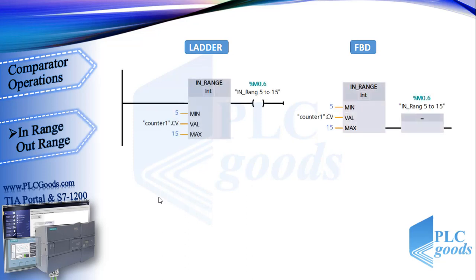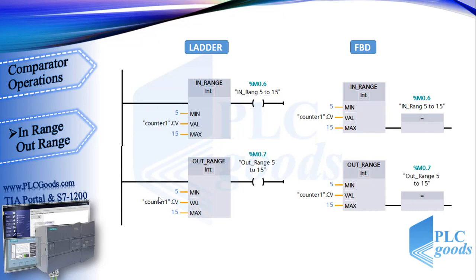Here we have in range and out range instructions. At the first line, when the counter value is a number from 5 to 15 — meaning 5, 6, up to 15 — the output will be on. The out range instruction works inversely: at the second line, the output will be on if the counter value is not a number from 5 to 15.